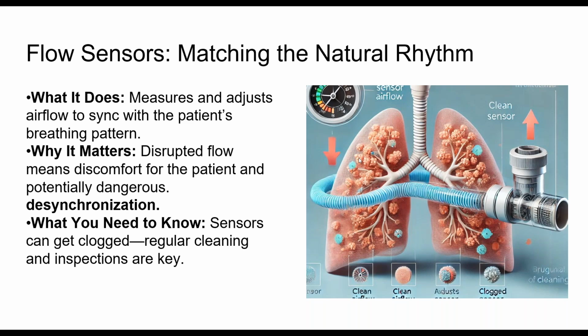But in critical care ventilators, remember, you've got a patient that typically can't breathe on their own or needs a lot of assistance in breathing. So you want to make those breaths as natural as possible. Airflow is critically important because you don't want to just blow in what is from the wall or from the tank immediately and constantly. But at the same time, you need to blow in enough air in any one breath or in any one millisecond. Disrupted flow can mean discomfort, right? It'll feel like somebody is choking, is starved, right? It's somewhat similar to volume, but volume is the result of those points in time. Flow is what's happening in essentially real time.